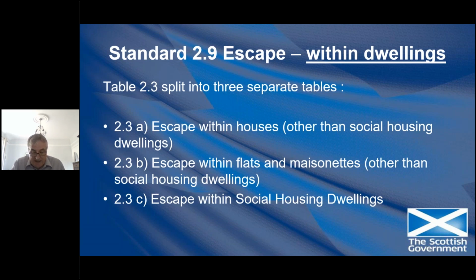2.3b, escape within flats and maisonettes other than social housing dwellings. This guidance has changed from that previously as a consequence of the mandatory standard of AFSS to all flats and maisonettes. Hence, early warning—for example an LD1 category detection throughout—is now an option to choose, or to provide a protected enclosure. There is no time to go through all of this today, but I would suggest it would be beneficial for you to look at all 3 tables closely.